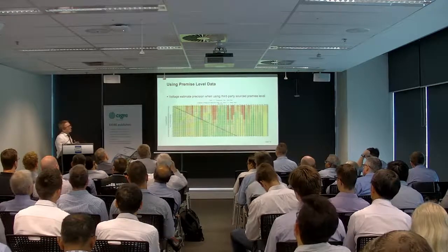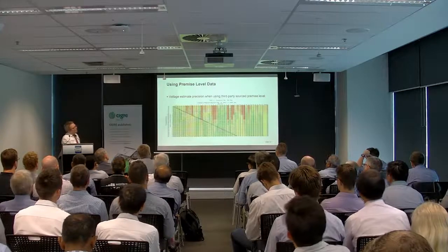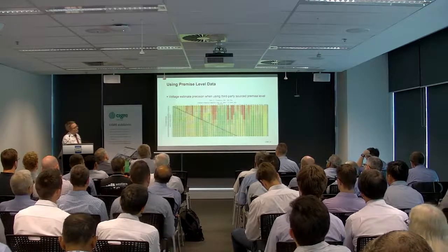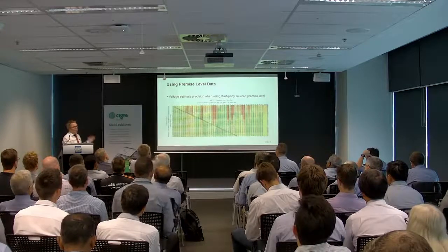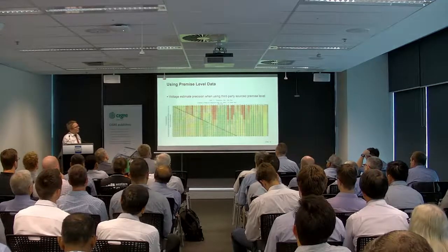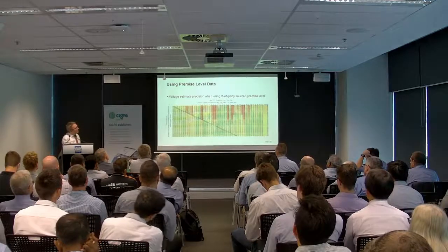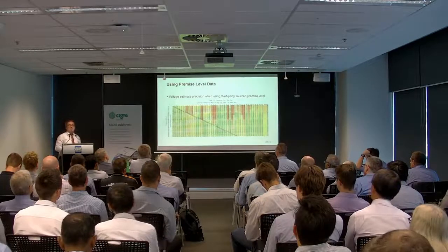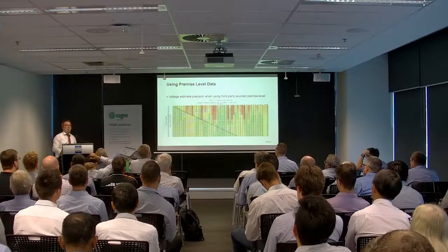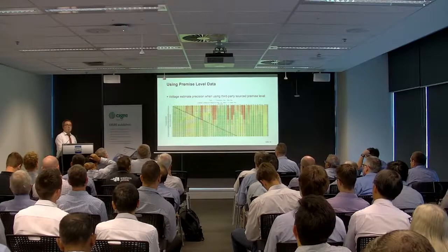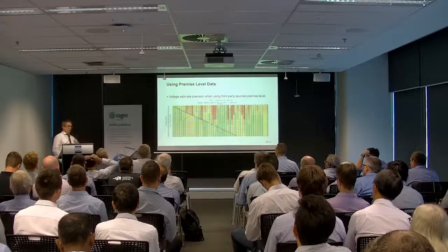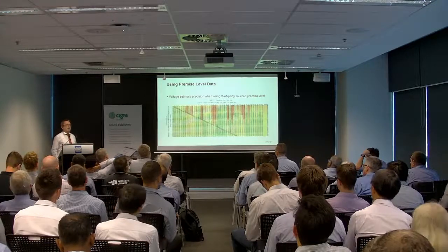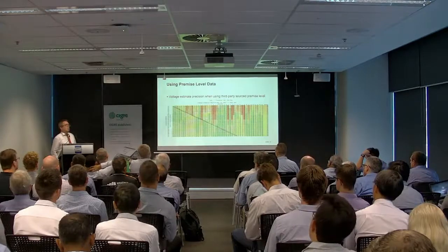The really interesting part is how quickly it more or less converges. This network supplies around 106 to 109 customers, a bit more than 100. If you have 19 or 20 measurements, that's about 20% coverage at premise level, and then you get next to zero marginal improvement on the estimate. So if the only thing you're after is the voltage profile of the LV network, you probably saturate at 15 to 20%. There's no point going to 100%.